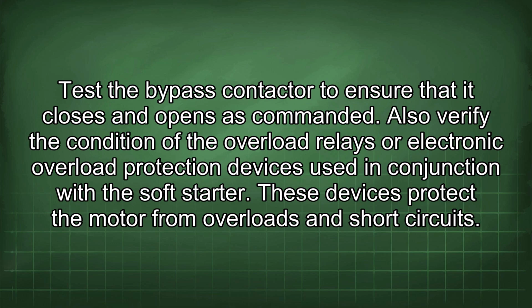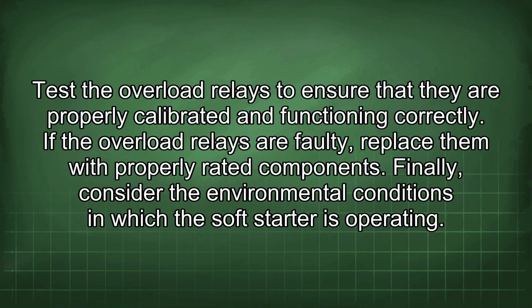Also verify the condition of the overload relays or electronic overload protection devices used in conjunction with the soft starter. These devices protect the motor from overloads and short circuits. Test the overload relays to ensure that they are properly calibrated and functioning correctly. If the overload relays are faulty, replace them with properly rated components.